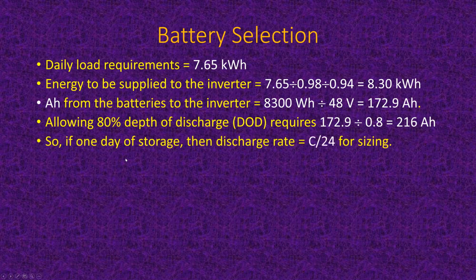All right. So if you just need 1 day of storage, then what you like to do is think about the fact that the faster you discharge a battery, the less useful electricity you get out, because there is internal resistance in these batteries. And the higher the current you draw, the more I squared R power loss you have inside the battery itself, not the inverter, inside the battery. So instead of the battery running loads, it heats itself up instead. So for 1 day's worth of use of the battery, that means you want to take 24 hours to discharge it, ideally. So let's see what that means.